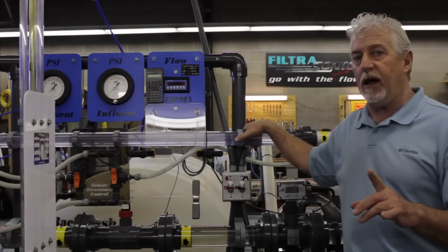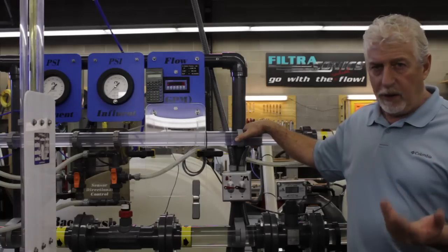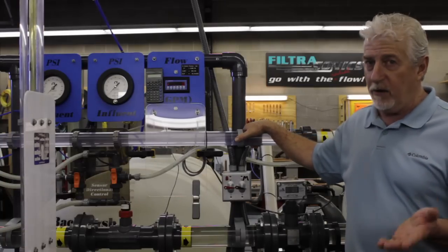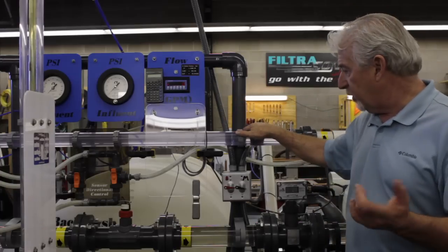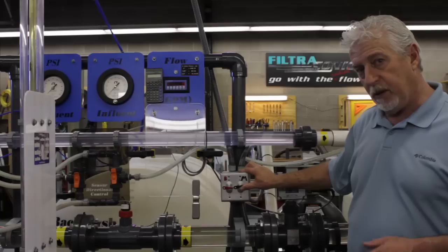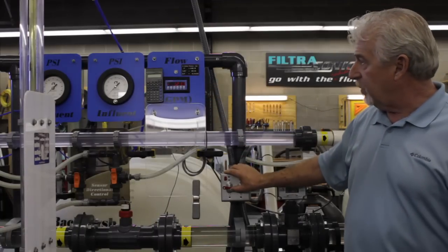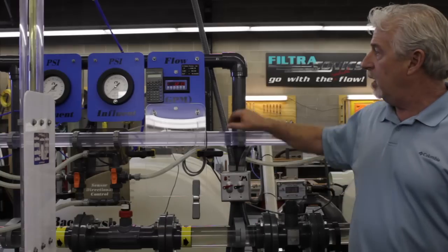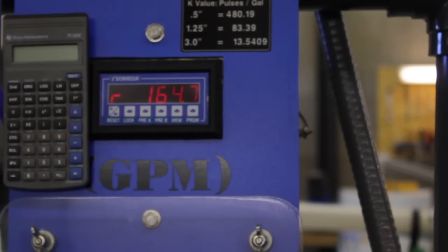We're going to run it right now, and today, due to the limitations of my pump capacity, we're only able to run at 165 gallons per minute, which you'll see on the flow meter. And we're doing that with 2 pumps. So first I'm going to kick on the main pump, and we'll come up to over 100 gallons per minute. Then I'm going to kick on the booster pump, and we should peak out right around 165 gallons per minute.